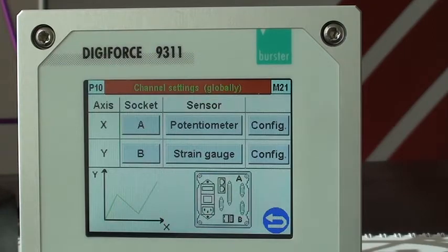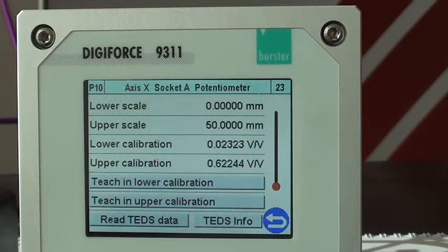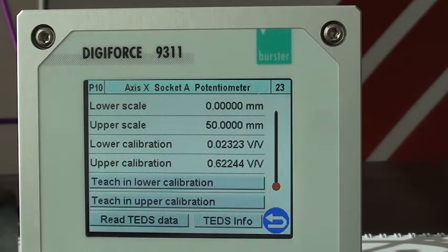We're going to do the axis X first, the potentiometer. Select Config. We're going to use a 50 millimeter linear displacement sensor. So make sure the lower and upper scale is set up correctly. Because this is a potentiometer, we have the ability to teach in the lower calibration and upper calibration.